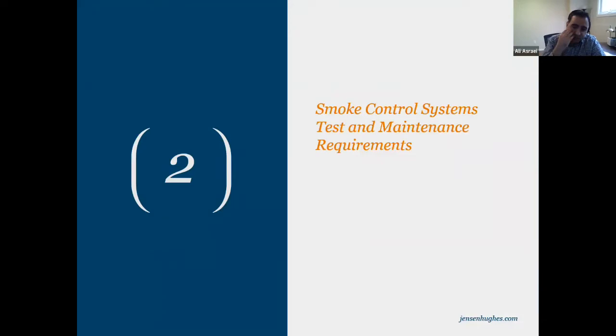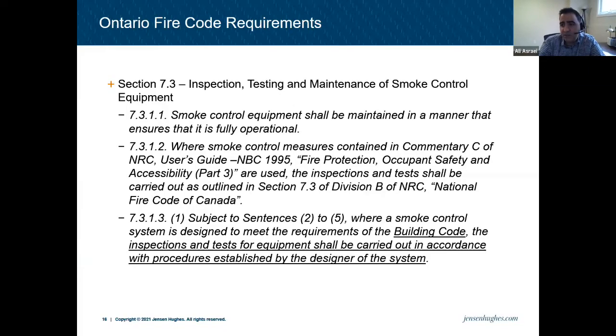Now let's talk about the test and maintenance requirements. Let's say we have that smoke control system in the building. It was tested, hopefully properly, and it worked and the building is occupied, and what are the requirements for test and maintenance? And where is it coming from? So obviously when the building is occupied, we're talking about the fire code here. So Ontario has certain requirements for this.